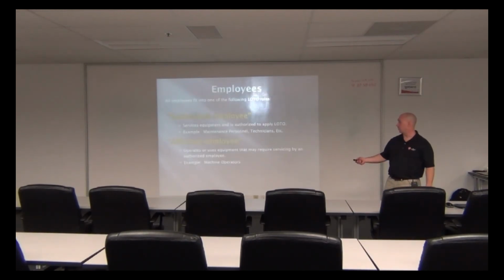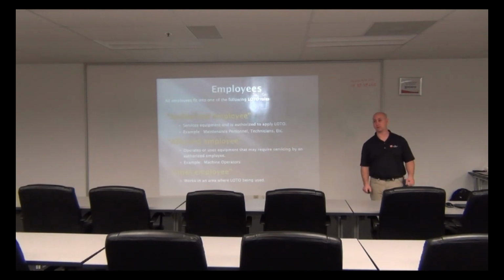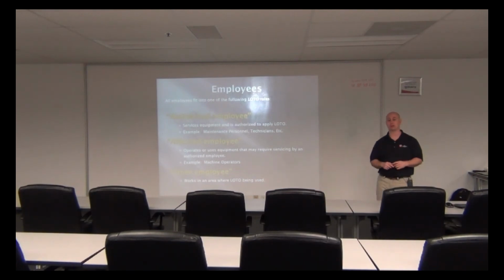So you've got different employees here. You've got an authorized employee, an affected employee, and other employees. The authorized employee is the person that does the lockout tagout, allowed to do that. They're the only people allowed to be working on that equipment, place a lock on it with a tag, and do maintenance on that equipment. The affected employee is potentially a person that actually operates that equipment, whatever it may be - they're the person that does that.